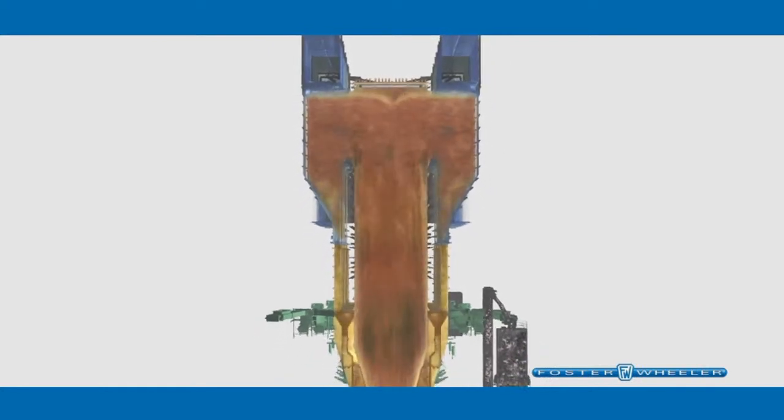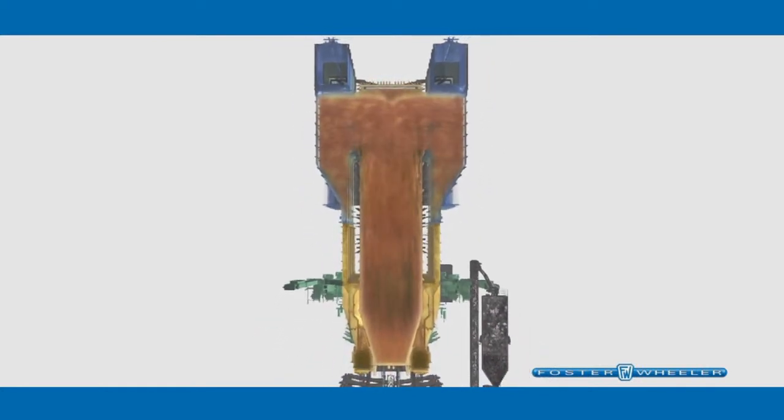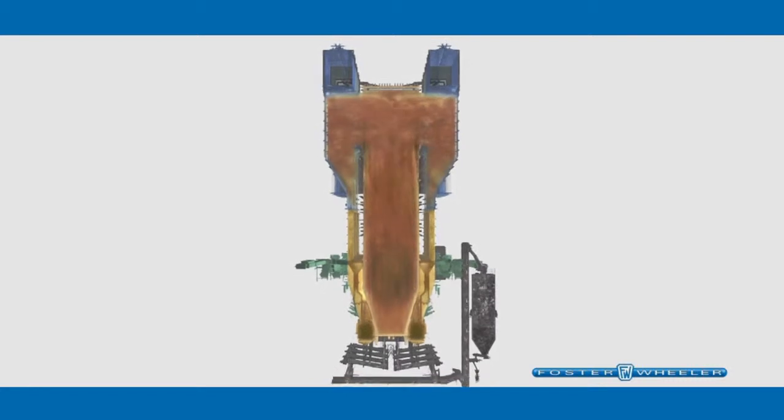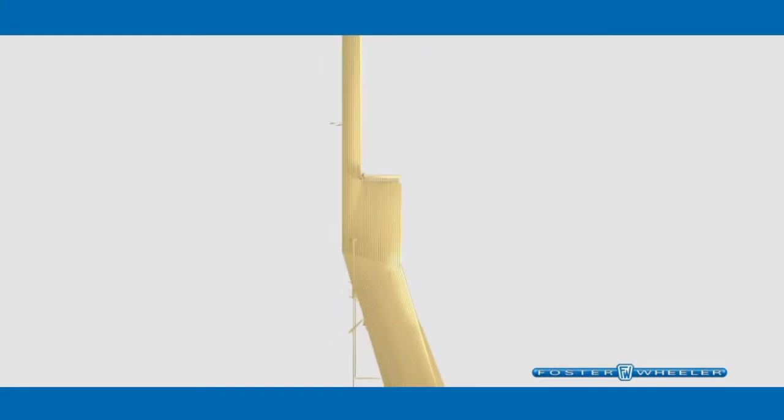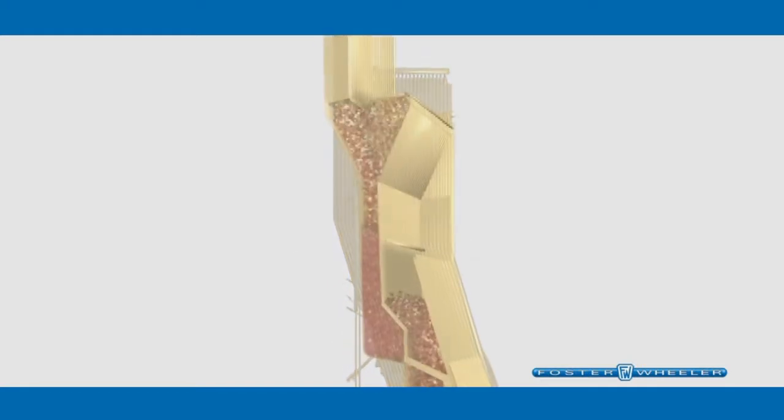Once separated from the hot furnace gas, the captured particles flow from the bottom of the solid separators and then into loop seals. The loop seals maintain the pressure balance between the furnace and the exit of the separators.